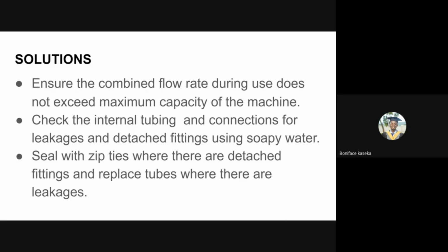You also need to check that the internal tubing and connections have no leakages or detached fittings, so you don't want to have any leakages. You can do that by just applying soapy water. What you normally do is switch on the apparatus, switch on the oxygen concentrator, and open all the outlets of the oxygen flow splitter. You open the oxygen flow splitter inside, and then you apply soapy water.